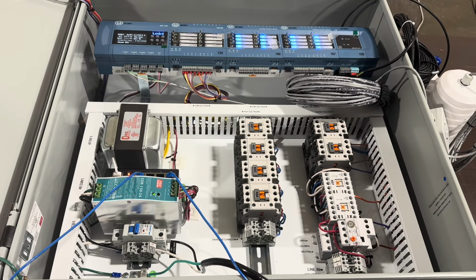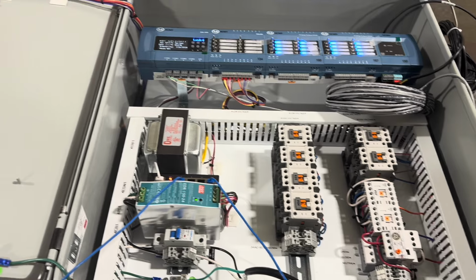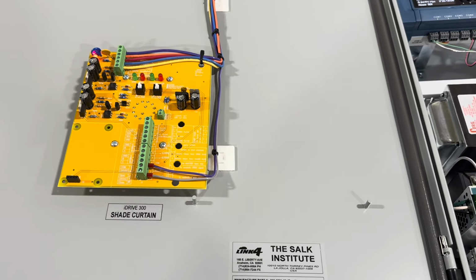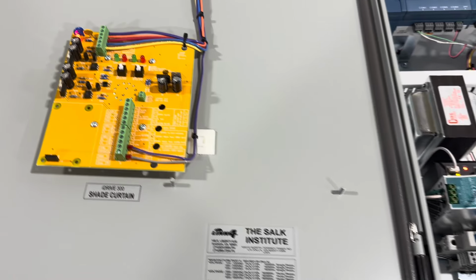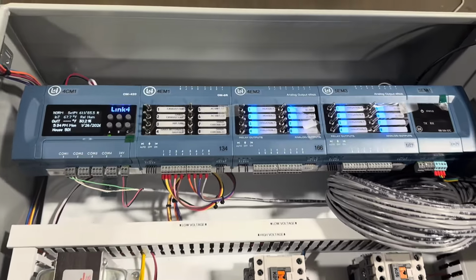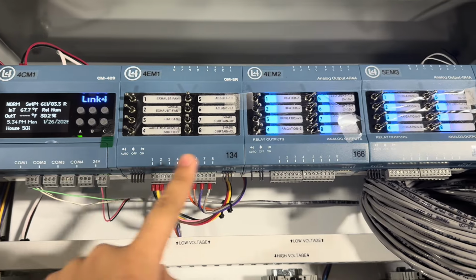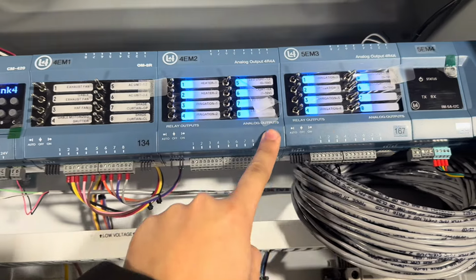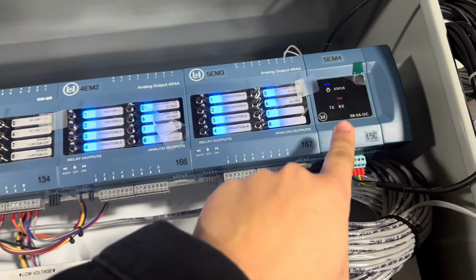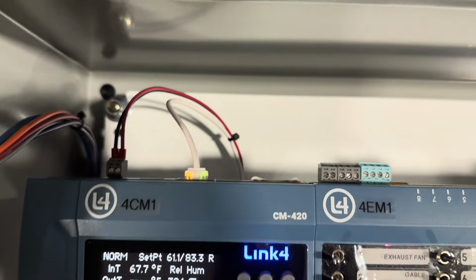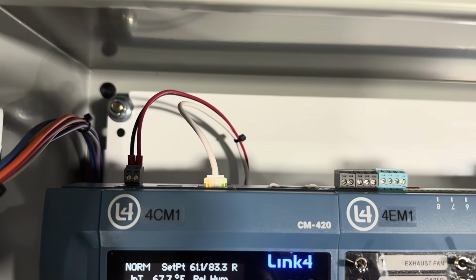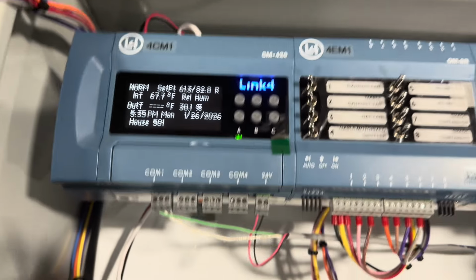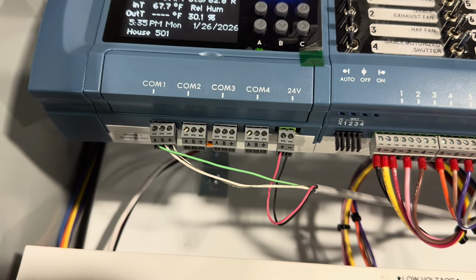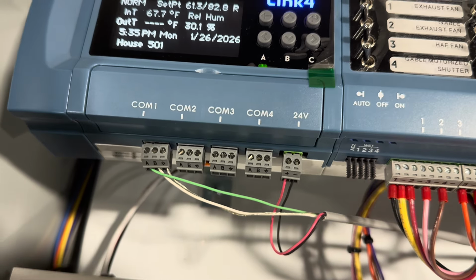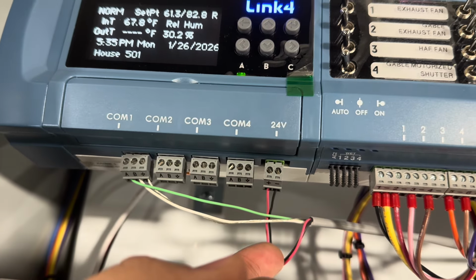This is the inside of the enclosure for Zone 1, House 501. We have a built-in iDrive 300 for the shade curtain. And on the inside, we can see the Pearl controller, our 8 output module, our 2 4R4A modules, and our 5 analog input module. The Pearl is powered by 24 volts DC coming from the top, and we also have an Ethernet connection. And on the bottom, we have a connection to the DTH. The DTH is connected to the Pearl on COM1 with these 3 communication wires and 2 power wires.